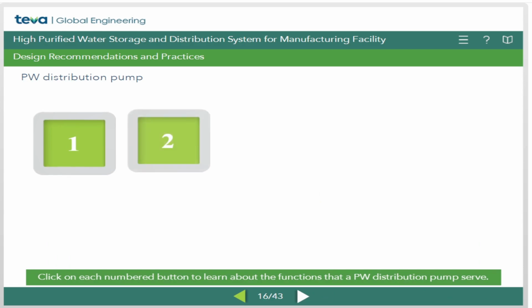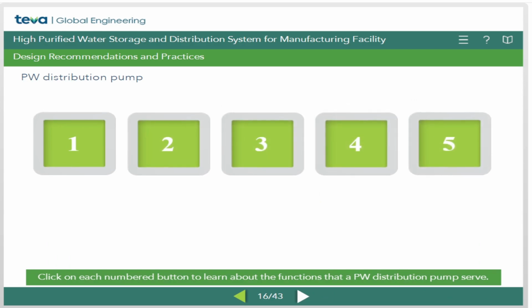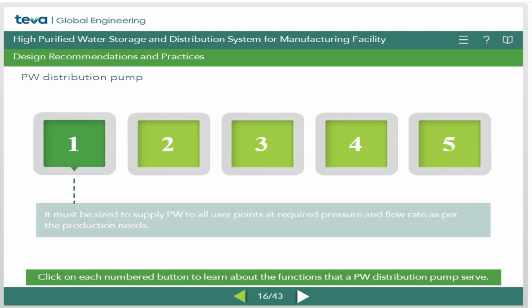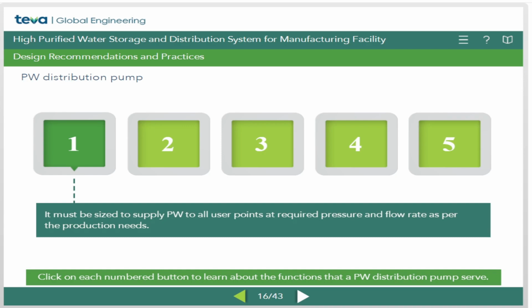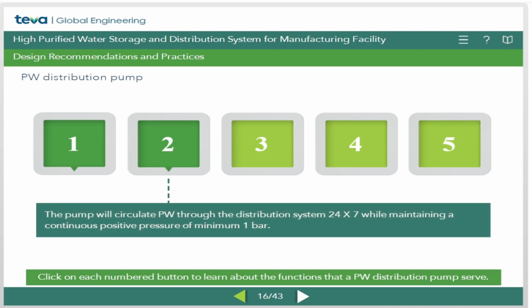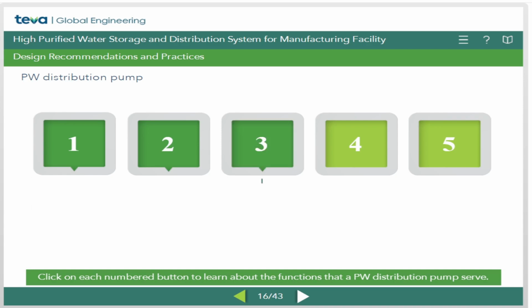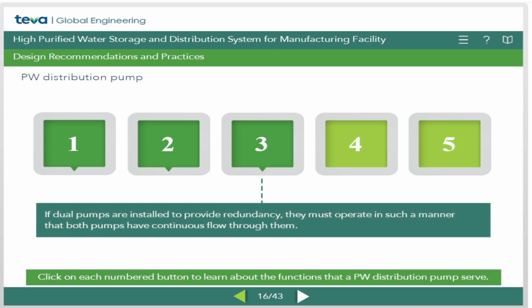To learn about the functions that a purified water distribution pump serves, click on each numbered button to learn. It must be sized to supply purified water to all user points at required pressure and flow rate as per the production needs. The pump will circulate purified water through the distribution system 24/7 while maintaining a continuous positive pressure of minimum 1 bar. If dual pumps are installed to provide redundancy, they must operate in such a manner that both pumps have continuous flow through them.